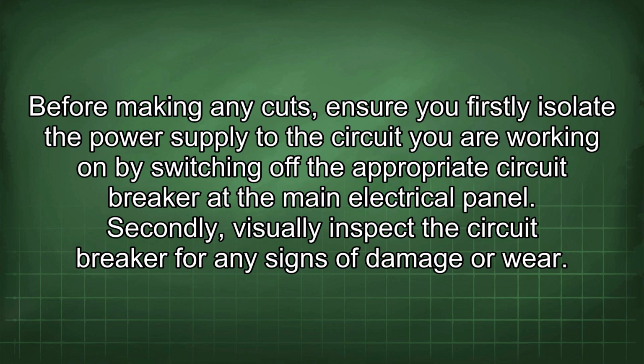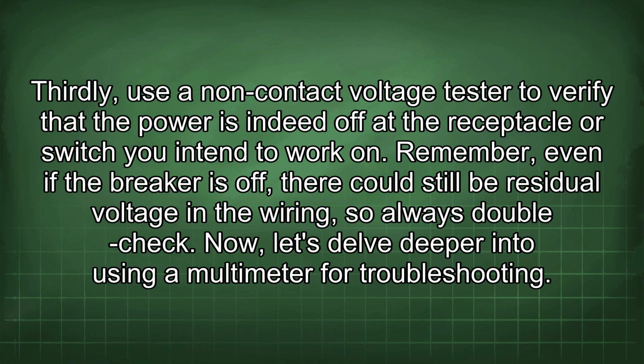Before making any cuts, ensure you firstly isolate the power supply to the circuit you are working on by switching off the appropriate circuit breaker at the main electrical panel. Secondly, visually inspect the circuit breaker for any signs of damage or wear. Thirdly, use a non-contact voltage tester to verify that the power is indeed off at the receptacle or switch you intend to work on. Remember, even if the breaker is off, there could still be residual voltage in the wiring, so always double check.